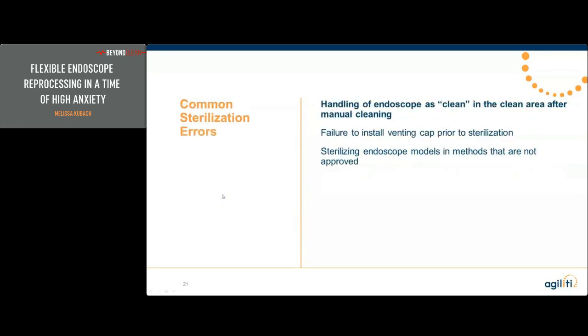Common sterilization errors: number one is handling of endoscopes as if they are clean in SPD after manual cleaning. So I understand that once it goes through that pass-through, you have to assume it's clean. But a lot of these endoscopes, I mean, they're not high-level disinfected. They've only achieved manual cleaning. So we haven't destroyed any spores or deactivated any spores. And I always warn everyone, hey, when you're taking this over to your clean area and when you're handling this, realize that this is not a clean item.